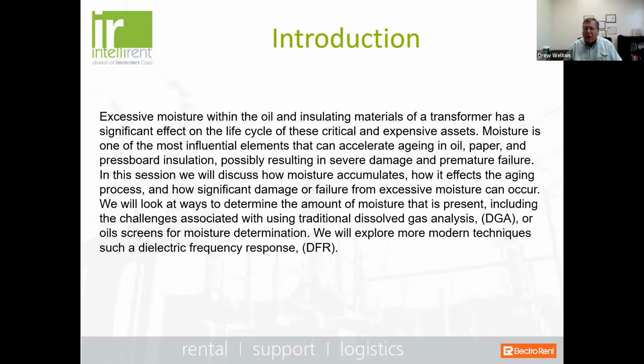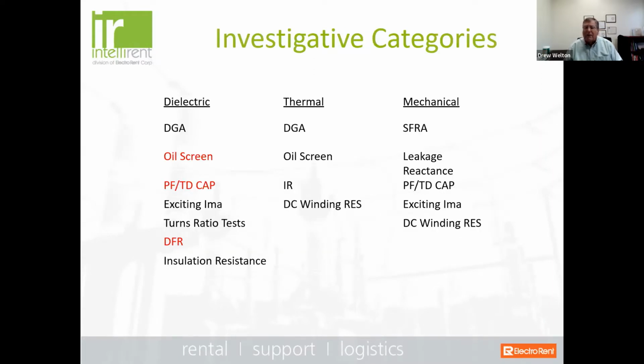Now, regarding excessive moisture, I'd like to talk about a couple of things. We want to talk about what the effects of excessive moisture are, where moisture comes from, and how we detect and determine the moisture content inside the transformer. And we're talking about the insulation system, and then some things that we could possibly do to mitigate this problem. When we talk about diagnostic testing of power transformers, there are three basic investigative categories. You have your dielectric, you have your thermal, and then you have your mechanical. And what I have here, of course, is a list of typical diagnostic tests that we do on a transformer to check the health.